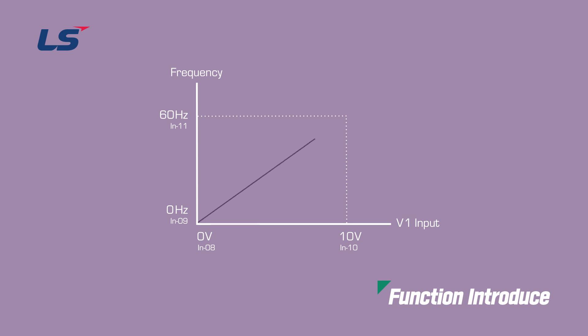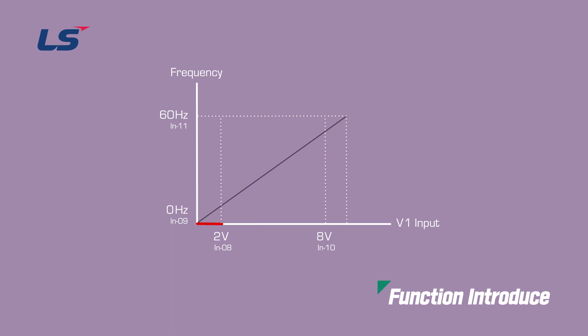For example, if the default is to stop at 0 Hz when 0 volts is input and operate at maximum frequency when 10 volts is input, you may want it to stop even when 2 volts is input, or operate at maximum frequency even if only 8 volts is input. In this case, you must set the frequency range for analog input.